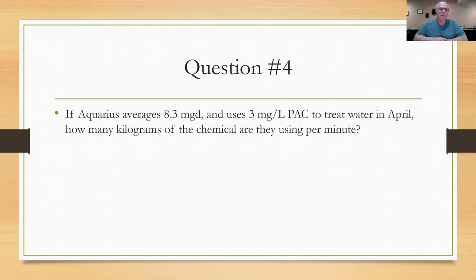Question number four is a little bit easy, but it does have a little kink to it. The Aquarius plant averages 8.3 MGD and uses 3 milligrams per liter powdered activated carbon to treat the water in April. How many kilograms of the chemical are they using per minute? So this is the basic dosage problem. You can work the pounds per day formula, but then you're going to take that pounds per day and convert it to kilograms per minute.